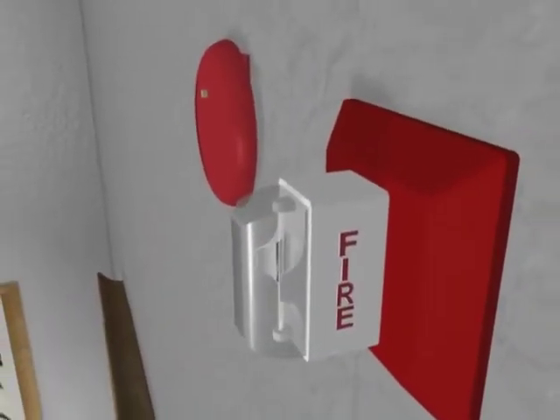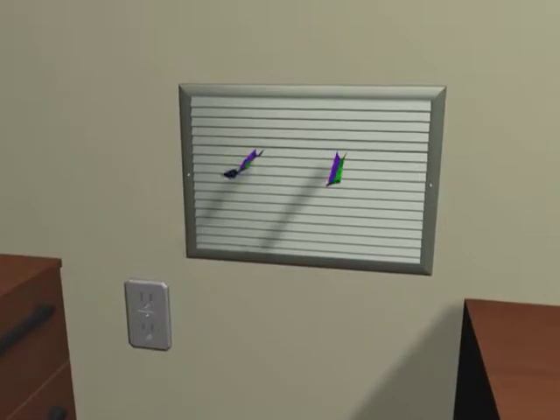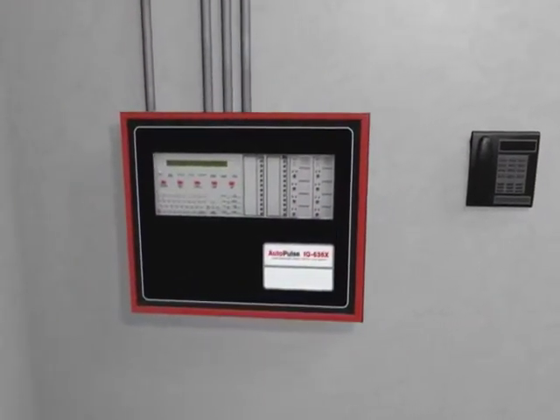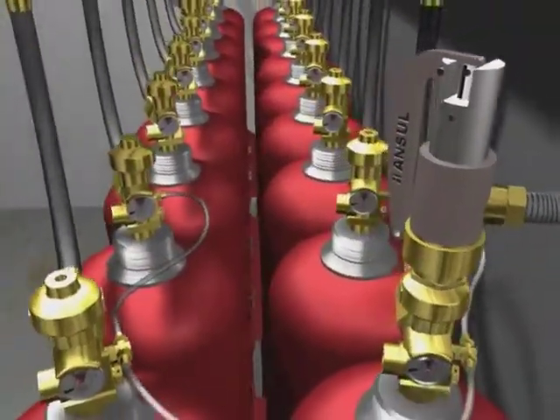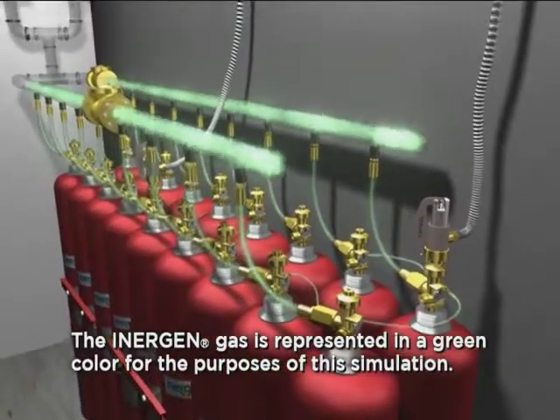Audio and visual alarms are started. The ventilation systems are closed off. After the prescribed time delayed period, the AutoPulse control unit energizes the electric actuator on the Inergen cylinder valve. The cylinder valve opens, allowing the Inergen agent to discharge from the storage cylinders.